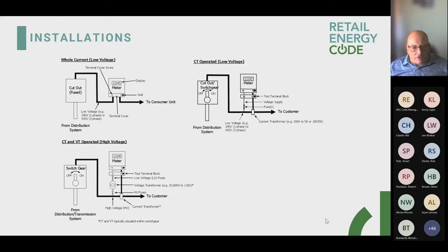So this time we have a current transformer on there and a voltage transformer. The voltage transformer will reduce the voltage down to 110 volts, and the current transformer will reduce it down to 5 amps. So on a 33,000 volt incoming supply, the transformers will take it down to 110 volts. If it's 11,000 volts, again they'll bring it down to 110 volts. So the conversions for the calculations are all done in the meter.